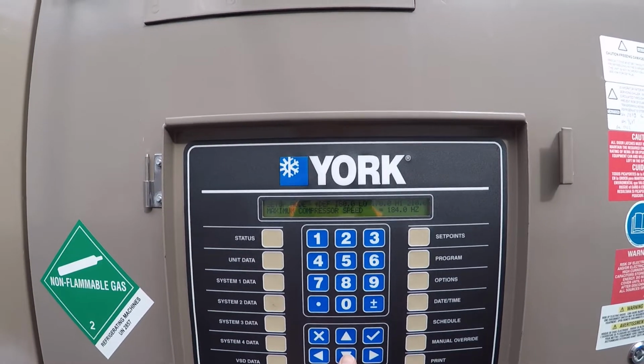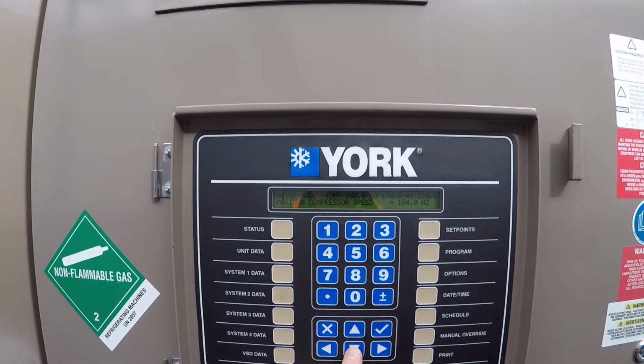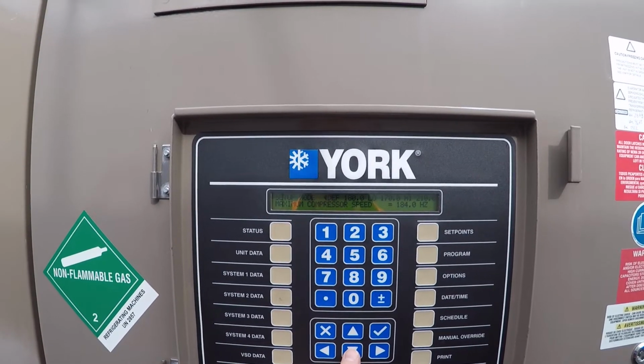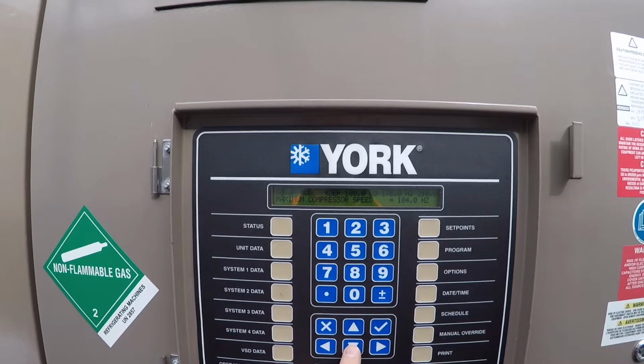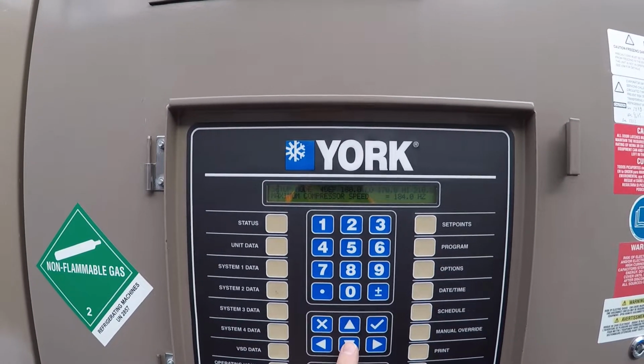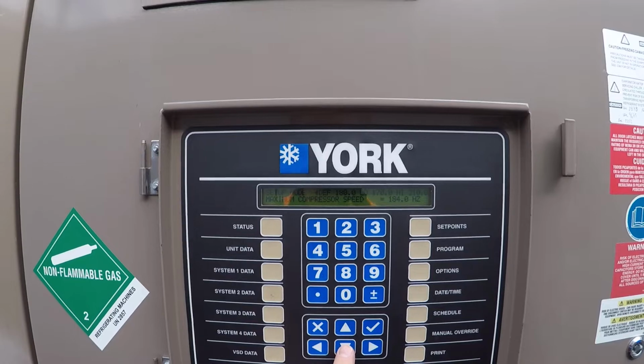So this is all the type of stuff you'd be doing and looking through and setting up when you're commissioning the unit. Maximum operating speed, because these compressors actually have a maximum operating speed, and you'd find that in the big book of knowledge that comes with the chiller. Normally it's already set up, but it's always good to check.